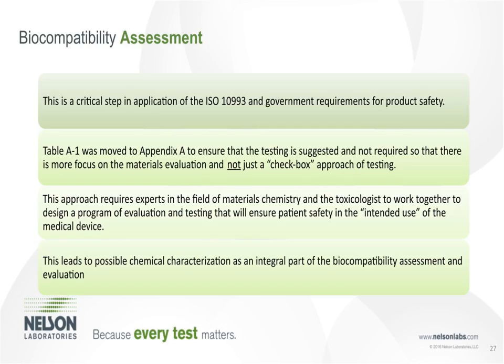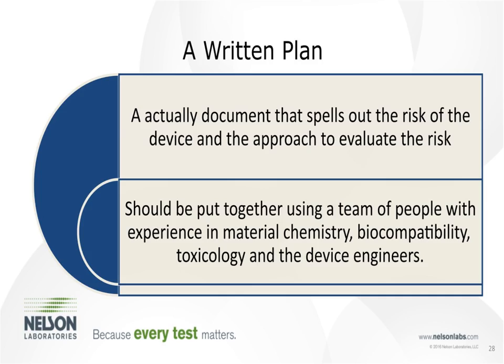That also leads to that chemical assessment, which is probably one of the most important parts of an evaluation, especially if it's a permanent contacting device, because without that chemistry evaluation, you're going to be stuck trying to evaluate genotoxicity, carcinogenicity, chronic toxicity, and reproductive toxicology through other means. So the chemistry becomes a much more important role in this new type of approach.